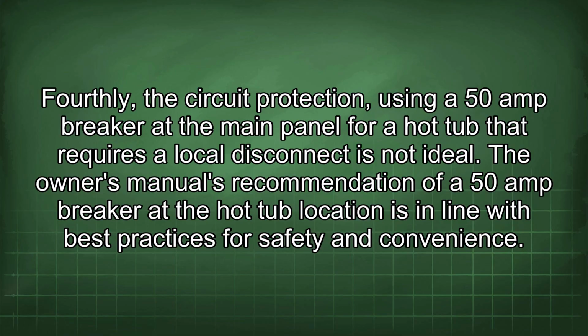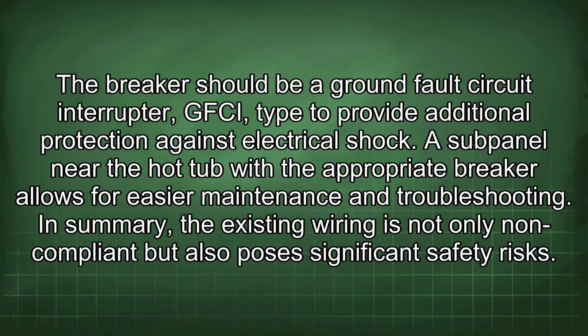The owner's manual's recommendation of a 50 amp breaker at the hot tub location is in line with best practices for safety and convenience. The breaker should be a ground fault circuit interrupter, GFCI type, to provide additional protection against electrical shock. A sub-panel near the hot tub with the appropriate breaker allows for easier maintenance and troubleshooting.